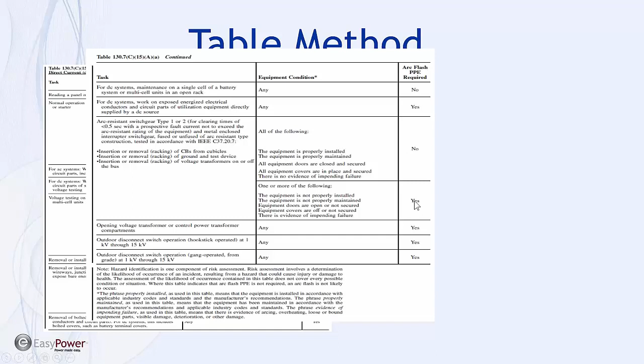We go through this table and look at each task that may be involved in any activity. As tasks become more complicated, or as covers are removed and we can't answer affirmatively on these five questions, we're directed to determine what PPE is required. To get there, we need to know the voltage level on the bus that's exposed, the short circuit current, and the clearing time. Based on those three factors, we can use this table to look up the PPE category for the operation we've decided to undertake.